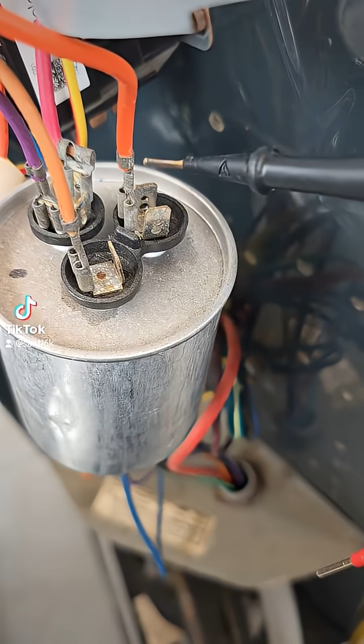Now, your common is always going to have 4 little prongs. Your Herm is always going to have 3 prongs. And then this side, which is your fan, is going to have 2 prongs. Unless you have a run capacitor, then you're only going to have 2, not 3. Now, if you have 2, it's much simpler. You're going to have 4 pieces on each side, but it's going to still be the same wiring setup.